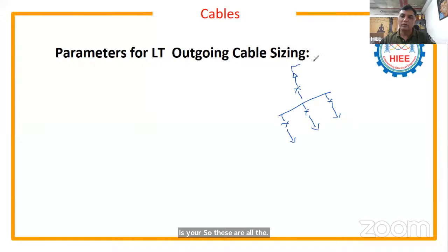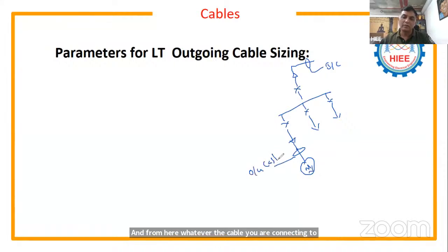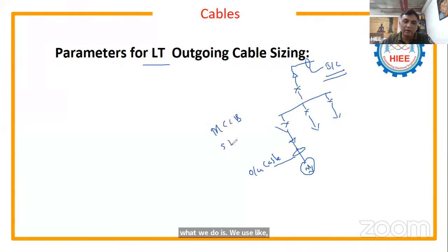So what we do, this is one cable, this is called the incoming cable, and from here, whatever cable you are connecting to the motor or whatever the application, this cable is an outgoing cable. Okay, so what parameters you should consider for outgoing cables and what parameters you should consider for incoming cables also differs, because in the outgoing cables mostly we use an MCCB or SDFU switch. MCCB stands for molded case circuit breaker. SDFU stands for switch disconnector fuse unit.